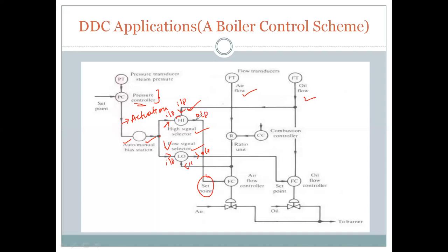The output of the high signal selector will give a set point for airflow, whereas the low signal selector output will give a set point for oil flow. To keep in mind: the signal is divided into two selectors — a high signal selector and a low signal selector. The output of the high signal selector gives the highest input as output, serving as a set point for airflow. The low signal selector output serves as a set point for oil flow.